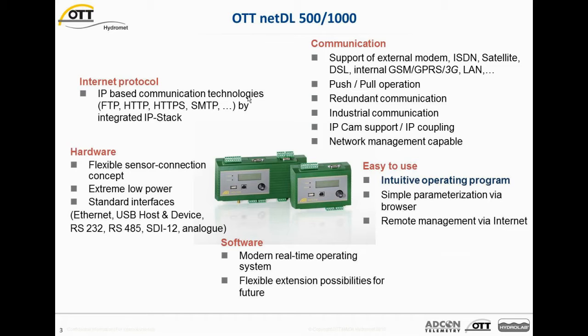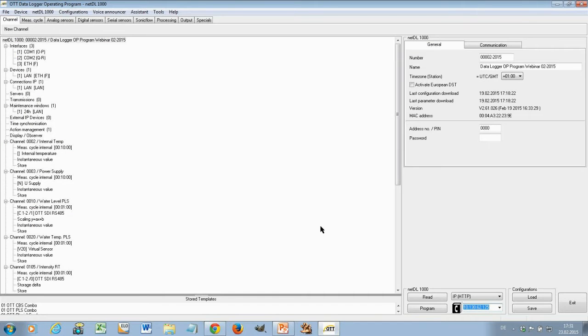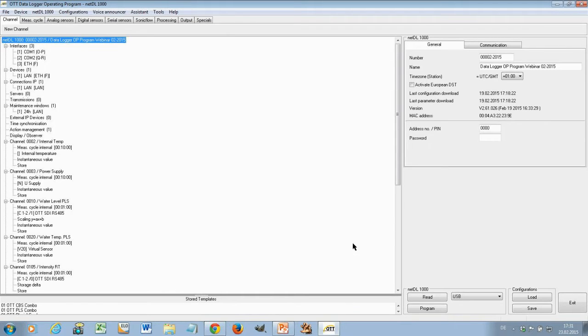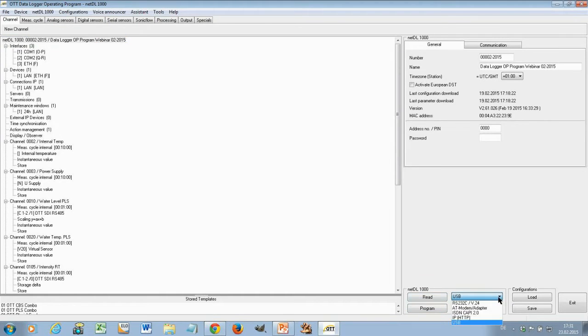Additionally, a simple parameterization via a browser is possible or remote management via the Internet. Now we come to the NetDL operating program. For this purpose, we open the program itself and establish a connection with a Data Logger. Now I'm reading in a configuration of a Data Logger at my desk. First of all, this is the view of the operating program. The communication with the Data Logger is done here. So there are various possibilities. There is USB and RS-232, which are typically local communication possibilities. That means I sit next to the Data Logger and I am connected via a USB cable or an RS-232 cable.